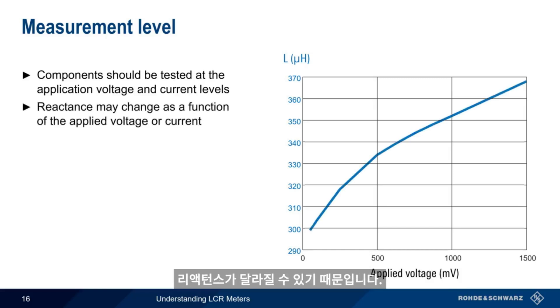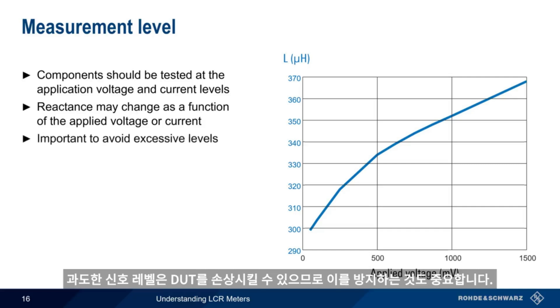Equally important is the level used in making measurements. Just as in the case of frequency, components should be tested at the voltage and/or current levels normally encountered in the intended application. This is because in many cases the reactance of a component may change depending on the level of voltage or current applied to it. It's also important to avoid excessive signal levels, since these can damage or destroy the component under test.